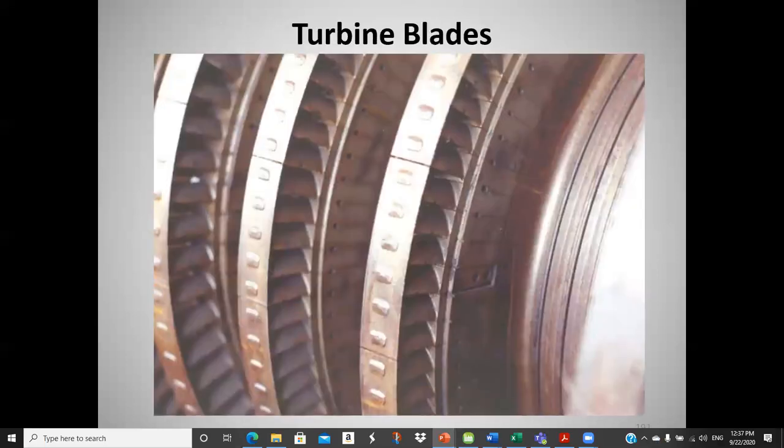That's an up-close picture of a TVA rotor. I don't know if you can see, some of those trailing edges of the blades are eroded away, where they have some solid particle erosion going on right in through here. Those particles have come off of the piping. It's magnetite, Fe3O4.